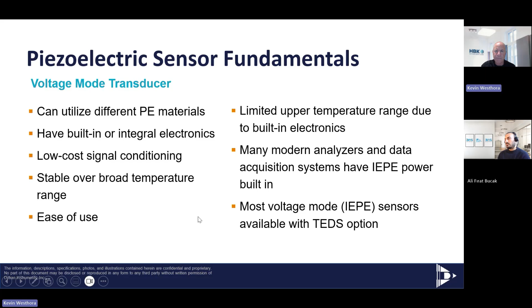All right, let's talk a little bit about IEPE, ICP, Isotron, Piezotron, CCLD, whatever you guys want to call it. They all mean the same thing, and this is what it means. It means that they have a voltage input. It's 18 to 24 volts DC, and it's 2 to 20 milliamp constant current. That's the key. So two things here that are very important to take away. IEPE accelerometers are constant current, 2 to 20 milliamp. Yes, there's a voltage associated, but the important part is it's constant current.